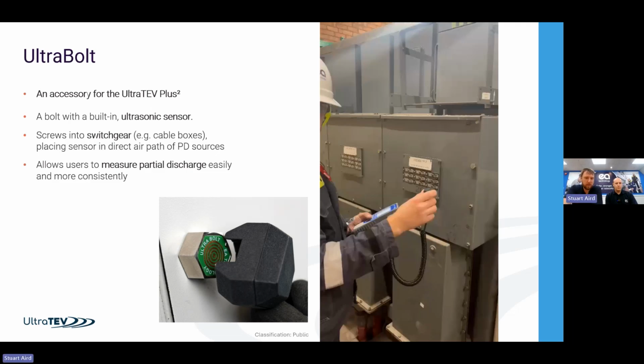This changes the story. So as you'll see from the video here, the bolt is mounted in the switchgear. There's a magnetic reader that clips on top, and the reading comes straight up on the device with the ability to hit record. That means that time after time, you're taking the reading in the same place. You can trend it. You're no longer recording by exception. That allows the data analysis to catch developing issues much easier and much earlier on, and also for you to get a better feel for how quickly things are deteriorating, because that consistency is there.